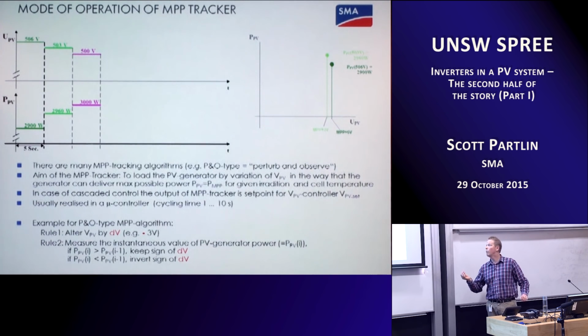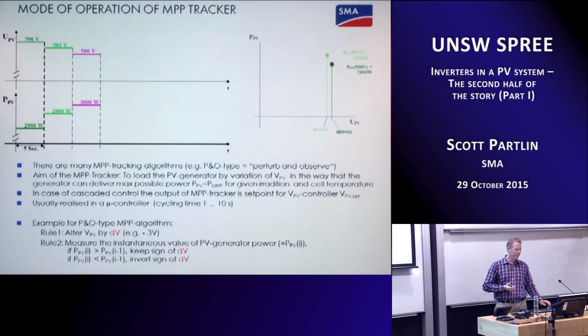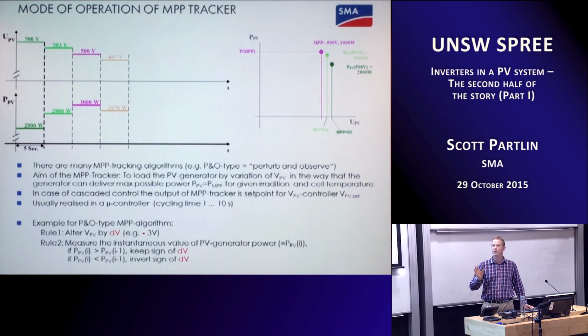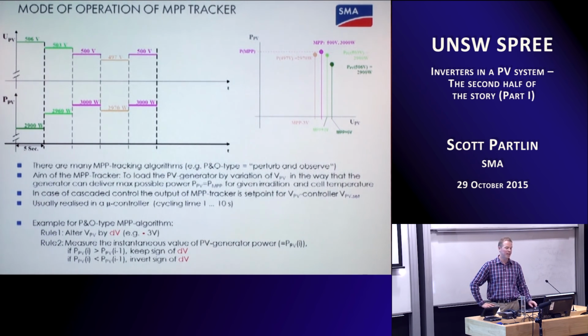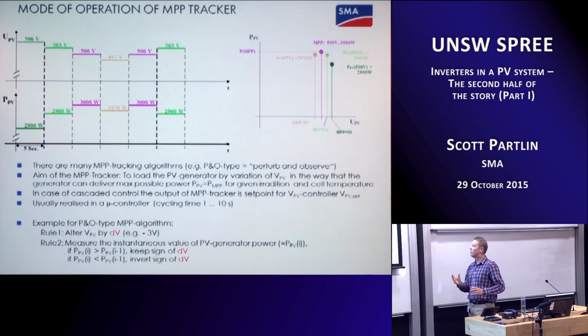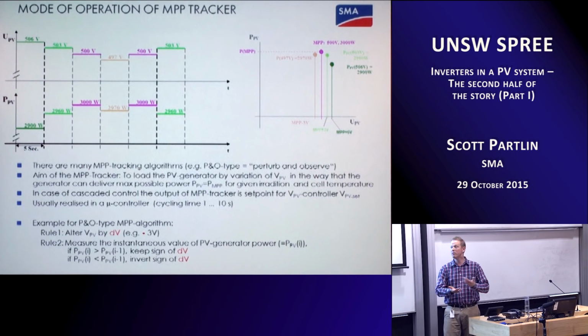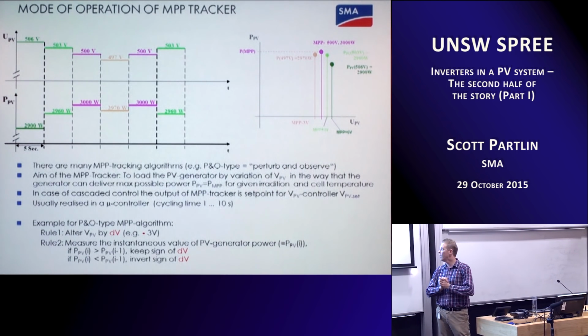Here I'm stepping through it very slowly. This happens within the inverter on millisecond to second time frames, where it continually pushes the voltage of the array around, tries to identify this maximum power point curve, works out where that point is, and then tries to hold it steady. If the PV system is sitting statically under a perfect light source, that's a really easy job.